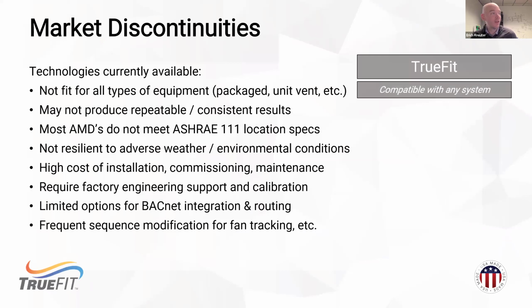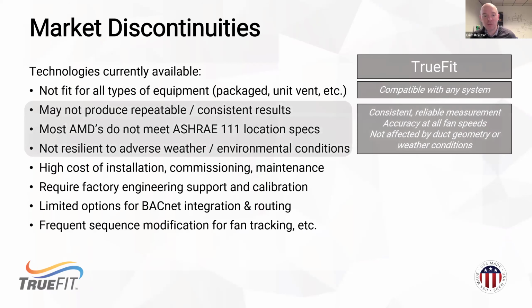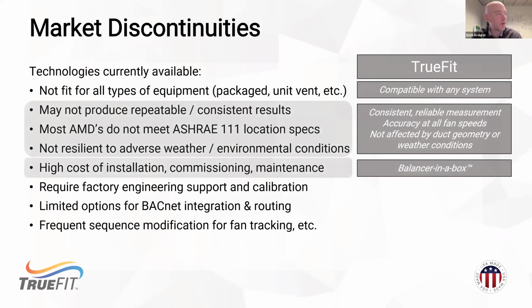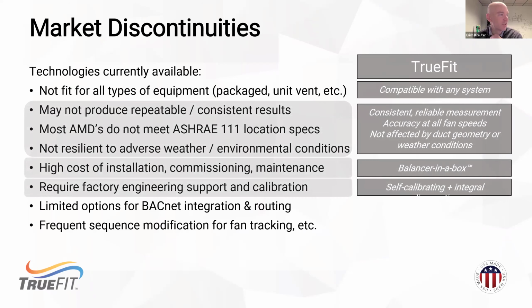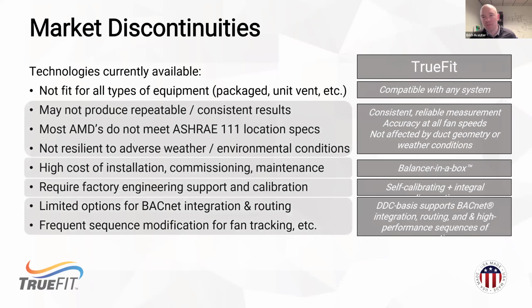So to wrap up here, several market technology challenges that we've covered briefly today. Not all airflow measurement is fit for all types of systems or restrictive ductwork. A lot of times they don't produce consistent results. None of them are based on ASHRAE 111, and a lot of times that leads to higher cost of ownership, whether that's installation, commissioning, or ongoing maintenance. They can have limited options for integrating into your control system.